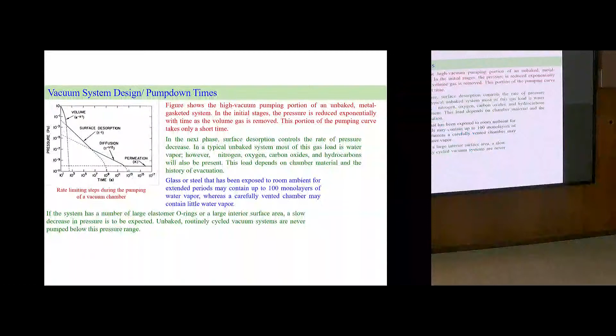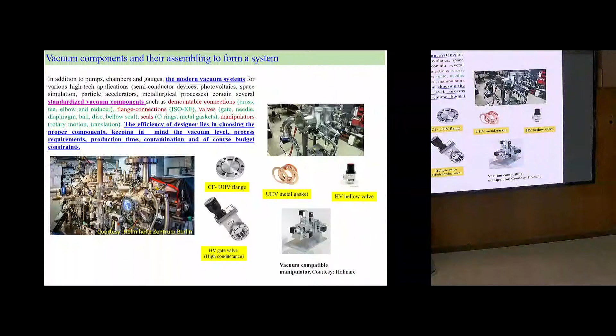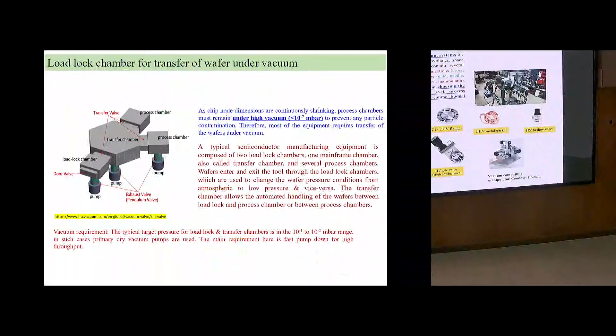This is how a typical UHV system in your display unit systems or anything will look. So, there are lots of components, all are vacuum components. This is a chamber, vacuum chamber and vacuum components. Anywhere there can be a leak. If there is a leak, you have to use a mass spectrometric leak detector, spray some helium gas, connect it and measure the leak detection. That I leave it to you. I have got the element, but you go through it on your own. Leak detection is a very important principle.